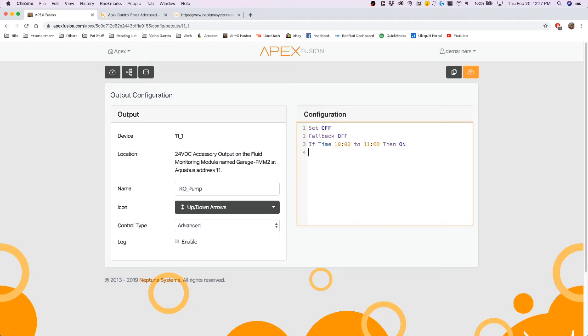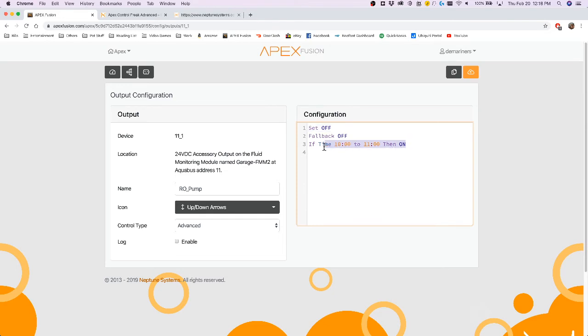So during the time of 10 a.m. to 11 a.m., this outlet will turn on. Otherwise, it will always be off. That is what the set off does, it sets everything off when any of the conditions below are not met.